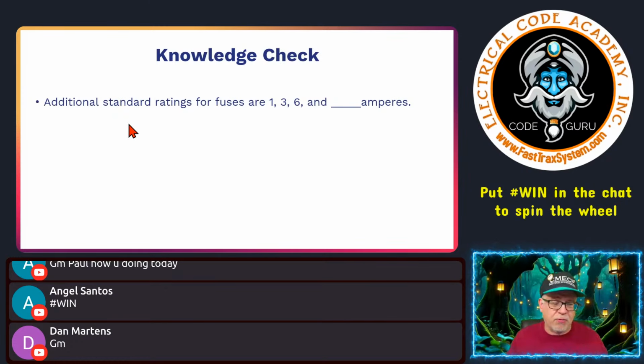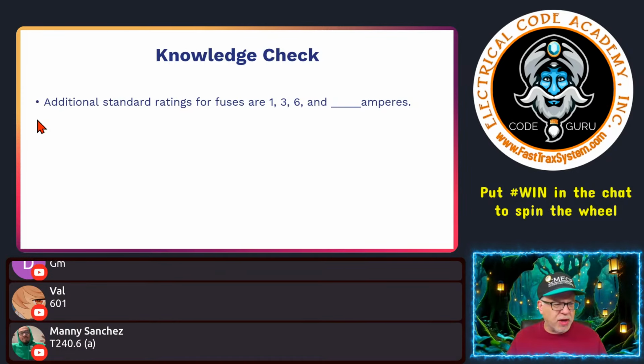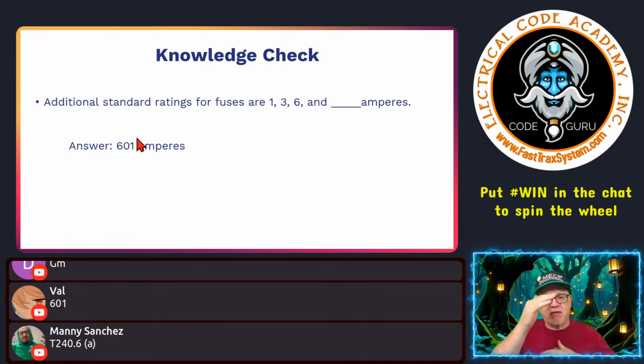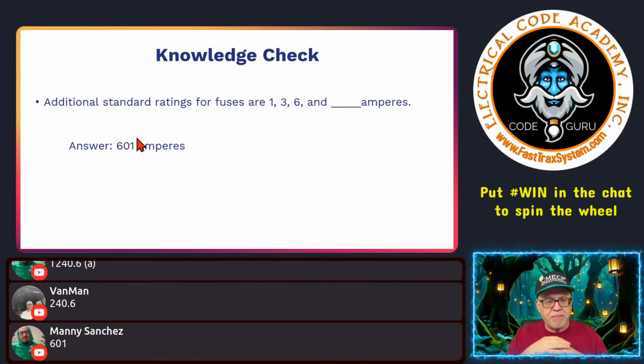And anybody know what the amp rating would be for the additional standard ratings for fuses? Anybody know? I know you were here yesterday. Y'all remember. There we go. 601, 240.6(A). That's what I'm talking about. So we're getting it in the house. So it's 601. 601 is designed for an 800 amp cutout box disconnect that is designed for a certain type of fuse that would fit. That would typically be designed for an 800 amp, but it allows us to put this 601 in there in an 800 amp frame and still use it on a 600 amp type system, those types of things.